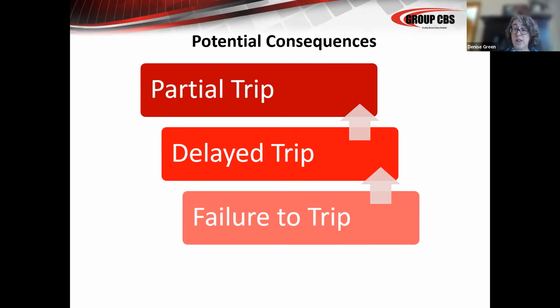It can happen at any voltage class, so it doesn't have to be at a medium voltage level. If a breaker, even a 480 breaker, trips and the gap is only 1/8 of an inch or 1/16 of an inch, you're going to have a situation where that arc does not extinguish when the phase is open. And now you get into that ionized air arc flash situation. So at that point, now you have damage to equipment, potential damage to personnel if anyone is there, downtime, and it's not quickly recoverable, like a delayed trip or a failure to trip. So that's the most severe consequence that can happen as a result of a partial trip on a breaker.